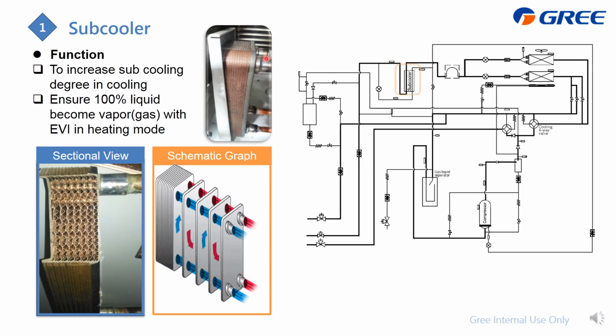And here is the appearance. Actually, it is a little bit small in size. And here is the detailed function for cooling, which is to increase the subcooling degree. And you can also see how we operate it. We divide the refrigerant into these 2 flows. This is the partial flow, which goes through this EXV and gets expanded. Then it becomes low pressure and temperature, so it can absorb heat from the main flow. Then the output becomes gas or vapor, and it flows back to the gas liquid separator. And we can also make the main flow temperature lower, which increases the subcooling temperature.